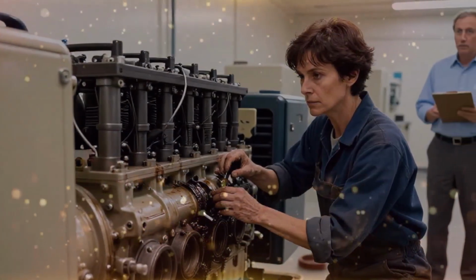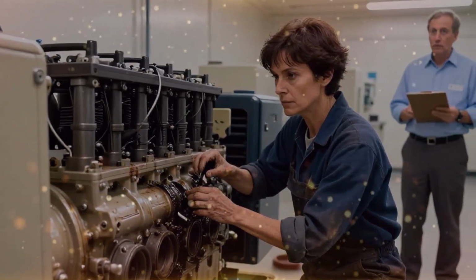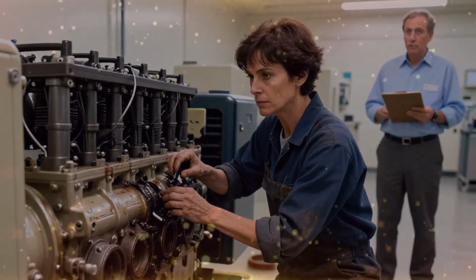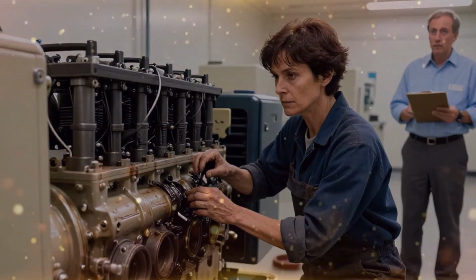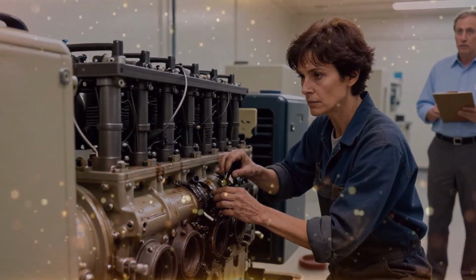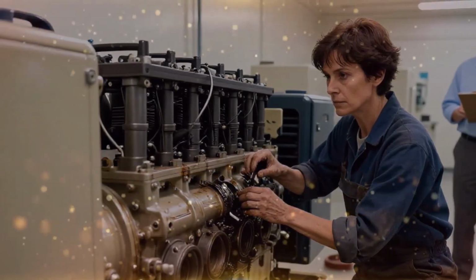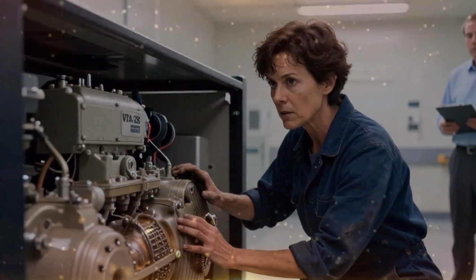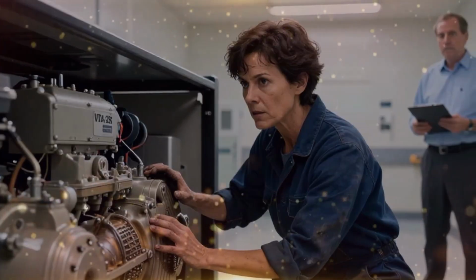They hadn't used a torque wrench. They had just cranked it down until it felt tight. On a machine like this, tight enough is a measurement of failure. Uneven torque on a flange warps the mating surface, introducing microscopic air gaps that destroy vacuum pressure.